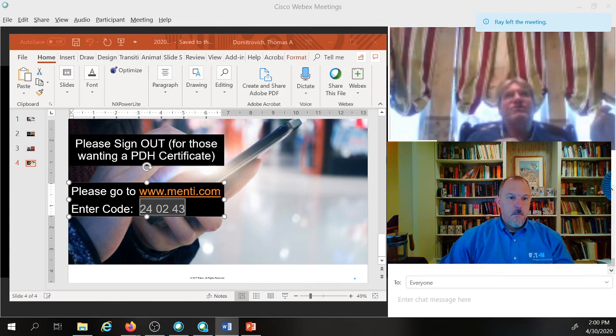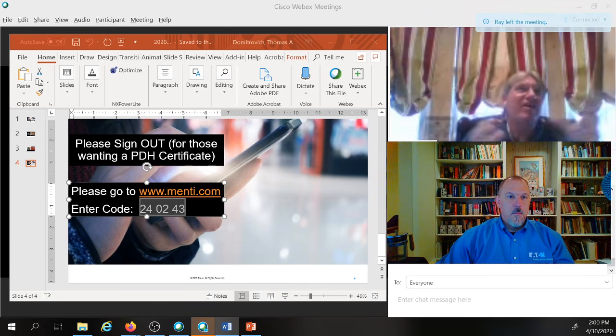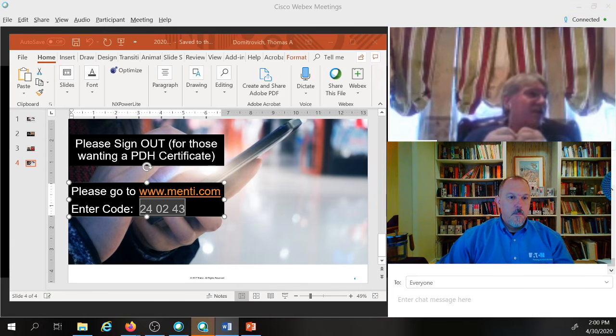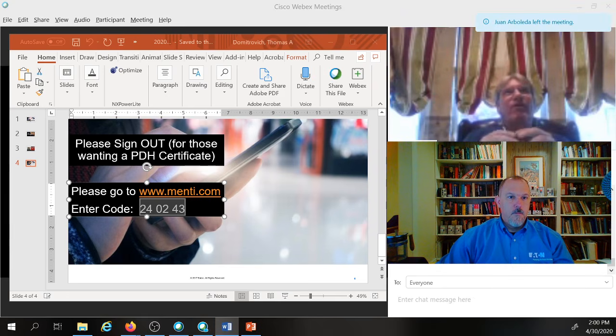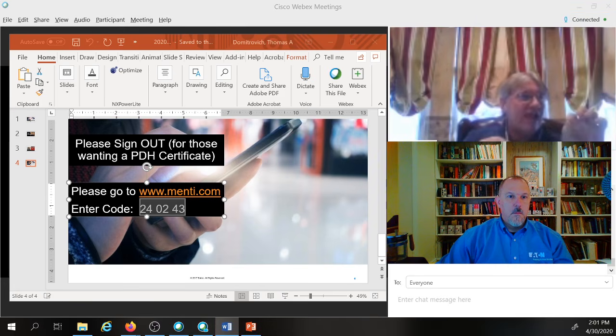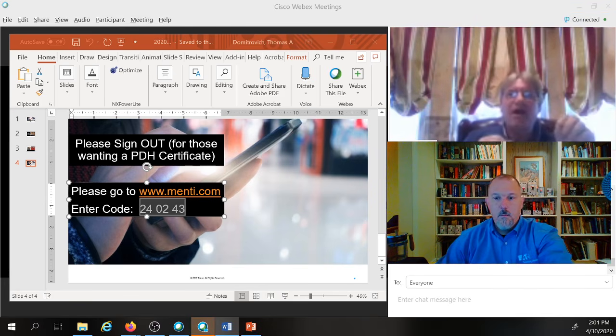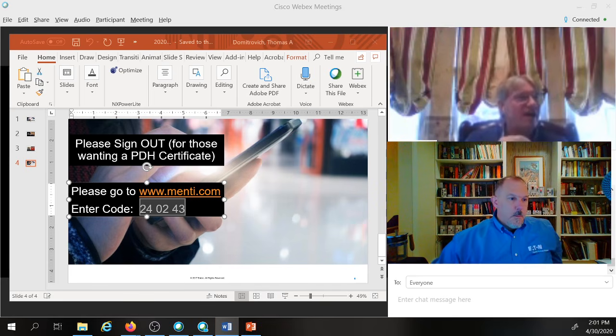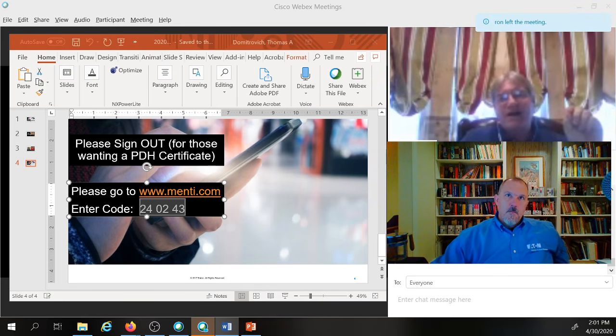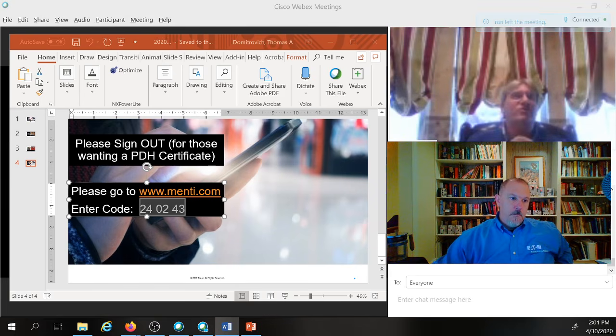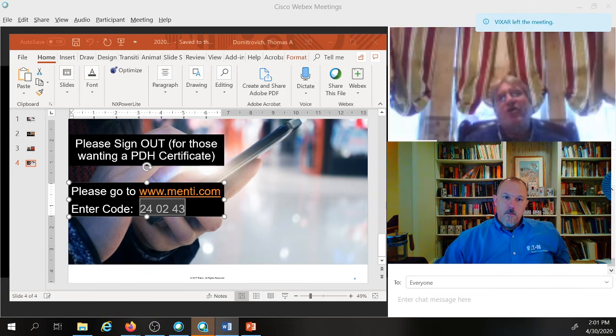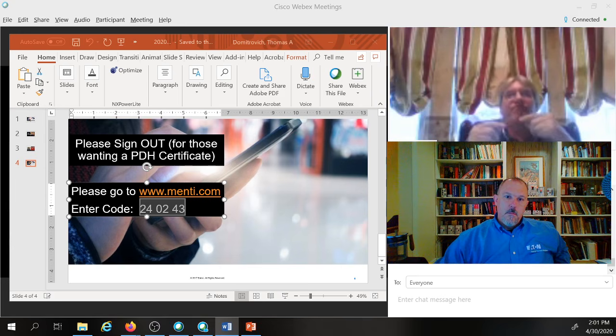You see a lot more factory sealed or encapsulated than you do hermetically sealed. For example, the factory sealed contact block could have air get into that contact block, but the area is so tight where the contacts open and close, you couldn't have a mixture that's going to have an explosion. Where the hermetically sealed, you can't. There's going to be no air getting into that because of the fused brazing that seals it.